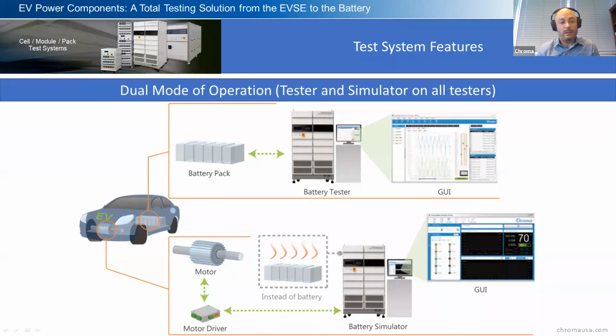Another way to use these products - what we call charge and discharge - is as a source and a load, with a regen load. You can go into constant current mode, say 25 amps, and we'll draw that current and put it back onto the grid. Or if you just want to use it as a straight DC source, we also have the ability to do that in constant voltage or constant current mode.